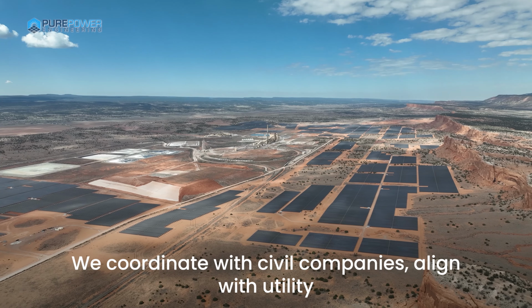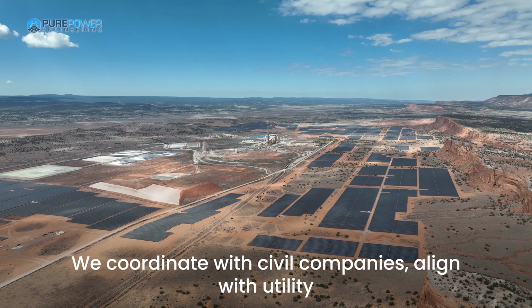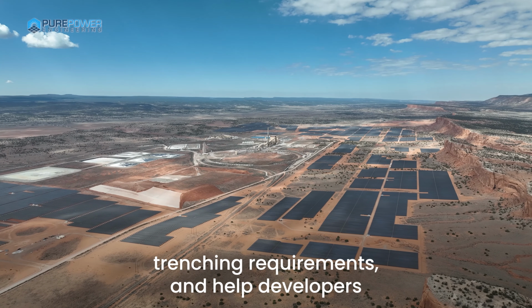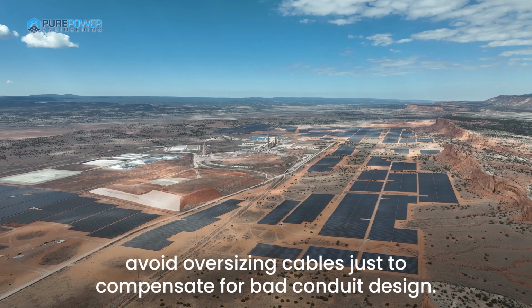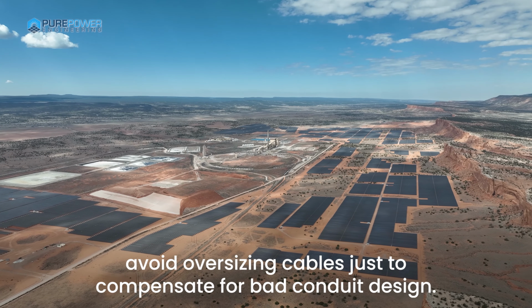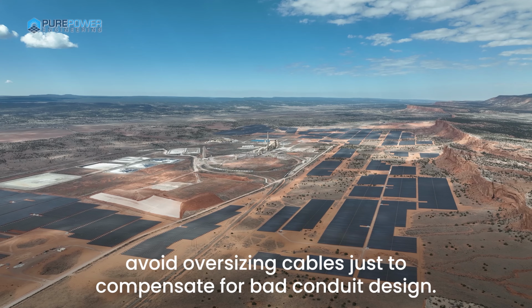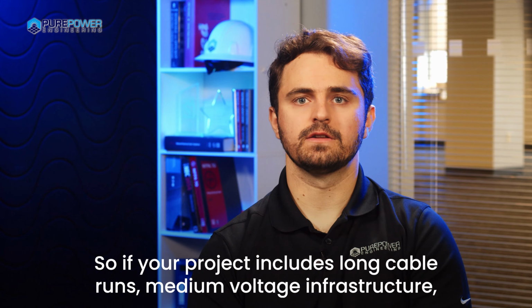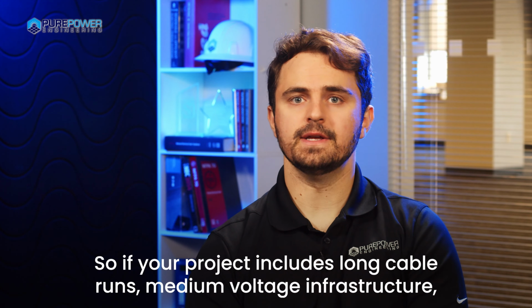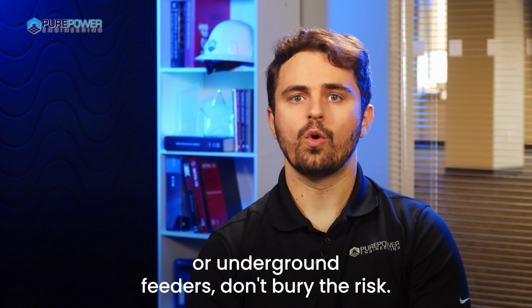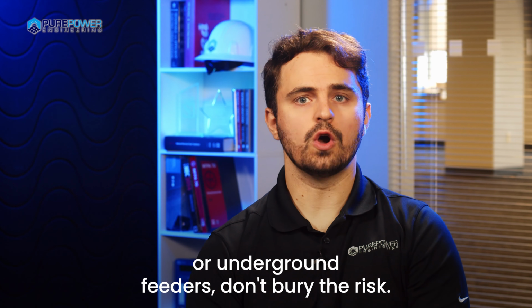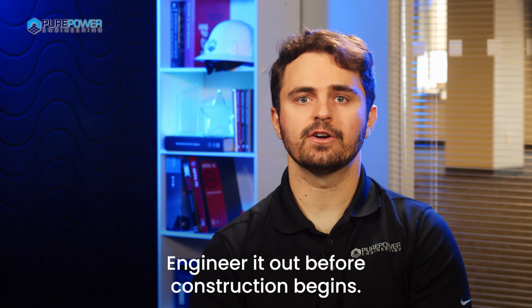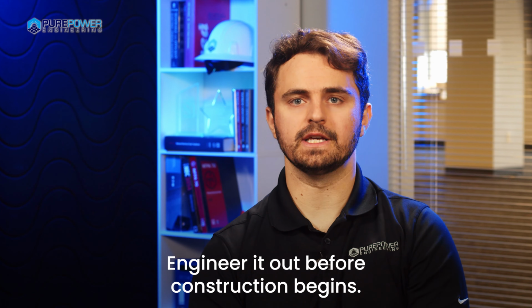We coordinate with civil companies, align with utility trenching requirements, and help developers avoid oversizing cables just to compensate for bad conduit design. So if your project includes long cable runs, medium voltage infrastructure, or underground feeders, don't bury the risk. Engineer it out before construction begins.